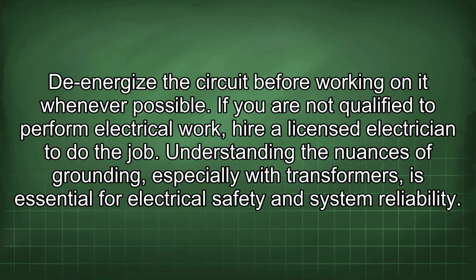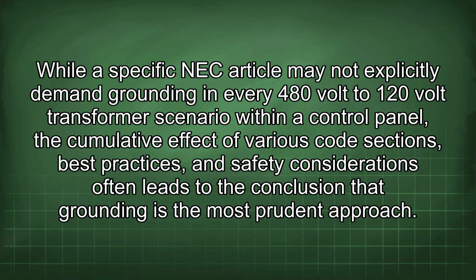Understanding the nuances of grounding, especially with transformers, is essential for electrical safety and system reliability. While a specific NEC article may not explicitly demand grounding in every 480-volt to 120-volt transformer scenario within a control panel, the cumulative effect of various code sections, best practices, and safety considerations often leads to the conclusion that grounding is the most prudent approach.